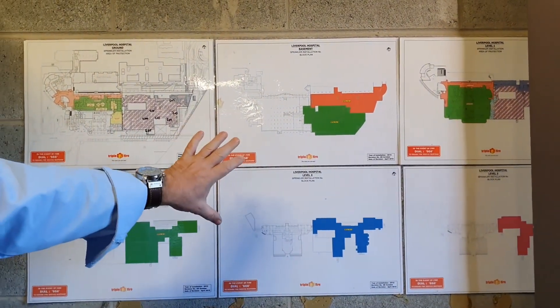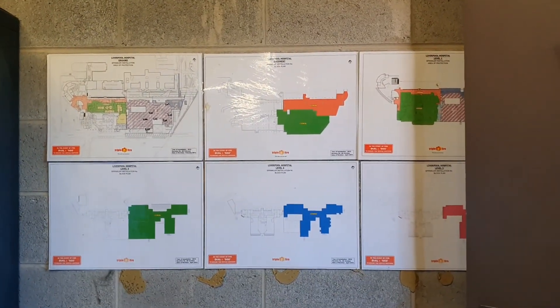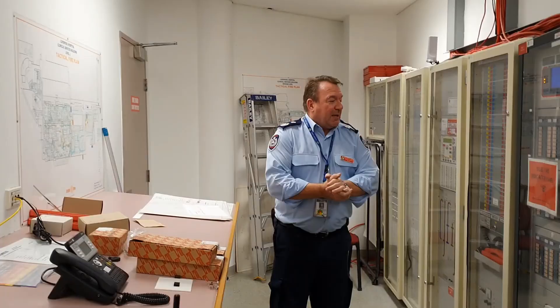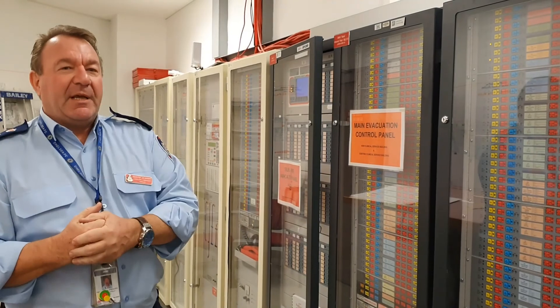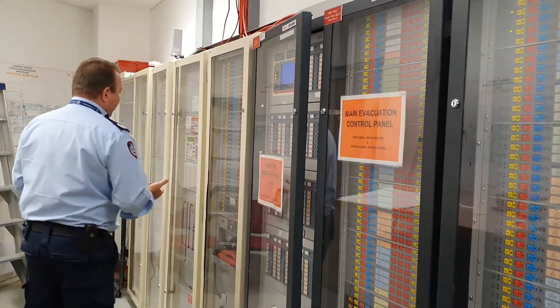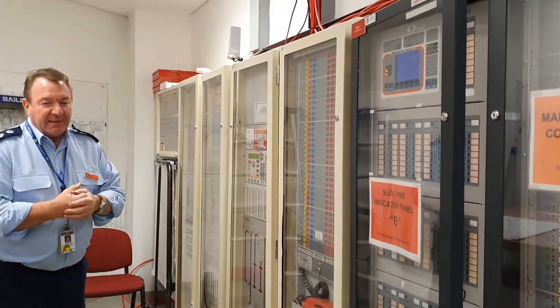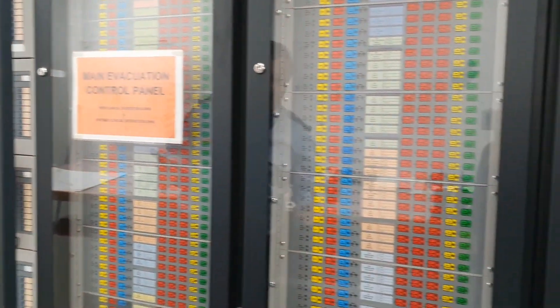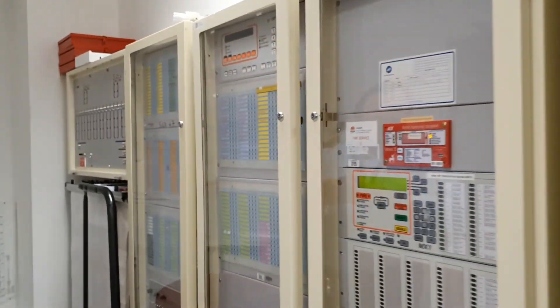These on here are block plans. The block plans show us exactly the zones that each alarm valve relates to and give us a basic location of where the valve is actuating. The detection system then pinpoints the exact area. So this is the main fire control room for Liverpool Hospital. There are in excess of 35,000 smoke detectors that come back to this room. To identify and locate a fire alarm, it comes back through one of these main fire panels, which is linked into 36 other sub-fire panels.